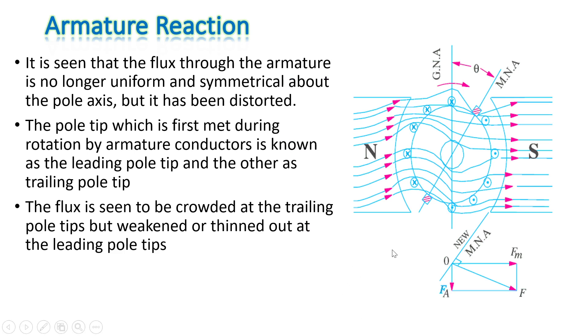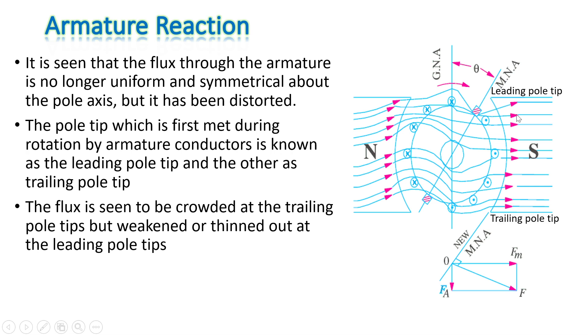This is the flux distribution when both fields exist simultaneously. The flux through the armature is no longer uniform and symmetrical about the pole axis — it has been distorted across the pole axis. If the armature rotates clockwise, the pole tip that conductors meet first is the leading pole tip, and the second is the trailing pole tip. Flux is seen to be crowded at the trailing pole tips and weakened or thinned out at the leading pole tips.